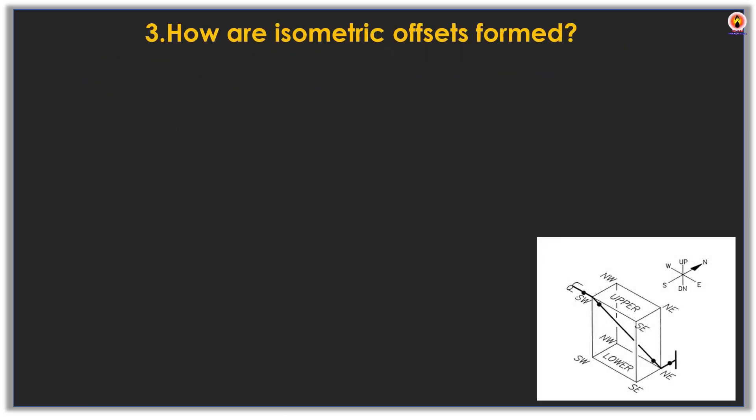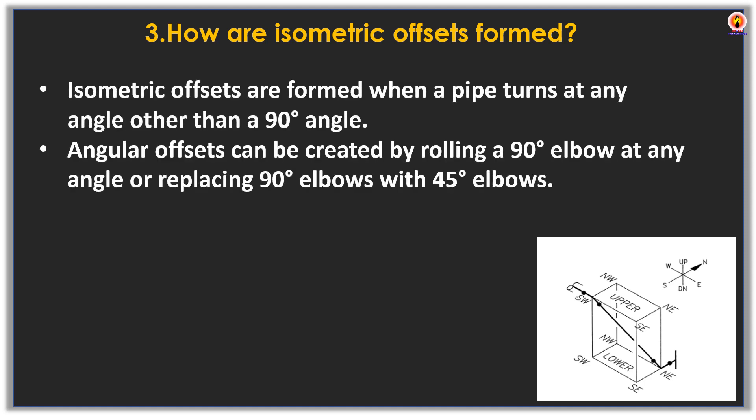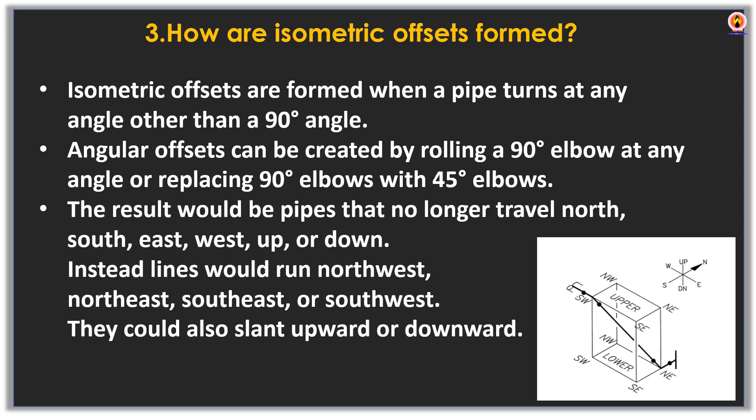Isometric offsets are formed when a pipe turns at any angle other than a 90-degree angle. Angular offsets can be created by rolling a 90-degree elbow at any angle, or by replacing 90-degree elbows with 45-degree elbows. The result is pipes that no longer travel north, south, east, west, up, or down — instead, lines would run northwest, northeast, southeast, or southwest, and could also slant upward or downward.